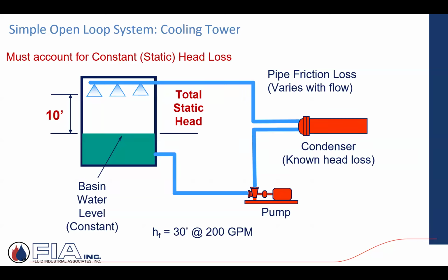A quick example here of an open loop cooling tower. If I'm going to develop a system curve, the whole thing isn't variable. That friction loss is variable. There is a fixed static head, a constant, and that's the way they refer to it. Account for the constant head loss. Well, that's that vertical lift. As I change this flow rate, that 10 feet doesn't go away. I still got to always account for that height, that static.